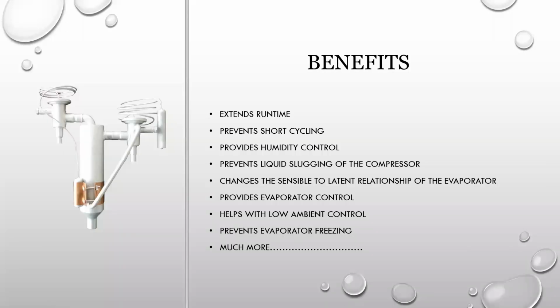Benefits of the RCCD. It extends the runtime. That is critical. It prevents short cycling. That saves equipment. By limiting the starts, you'll have extended life. Provides humidity control. By raising the saturated suction pressure, it allows for extended runtime, which we know will help control humidity and was seen in the next slide or two.